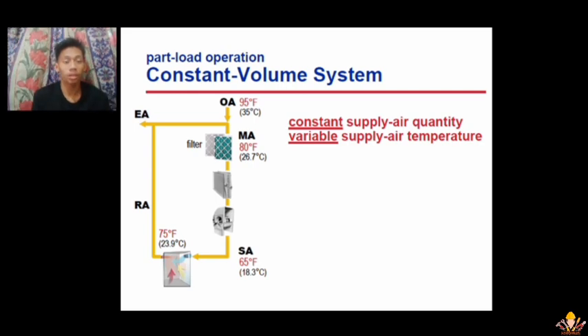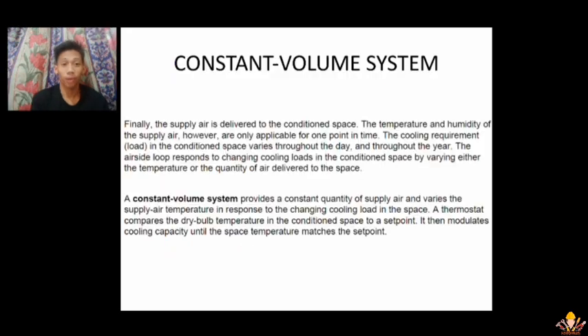We have the part load operation, the constant volume system, or CVS. The supply air quantity is constant and the supply air temperature is variable. Finally, the supply air is delivered to the conditioned space. The temperature and humidity of the supply air, however, are only applicable for one point in time. A constant volume system provides a constant quantity of supply air and varies the supply air temperature in response to the changing cooling load in the space.